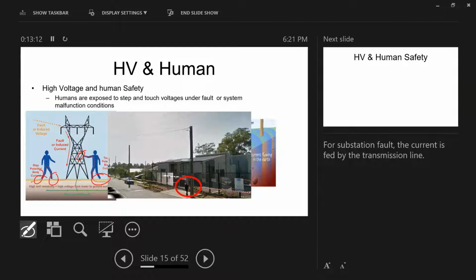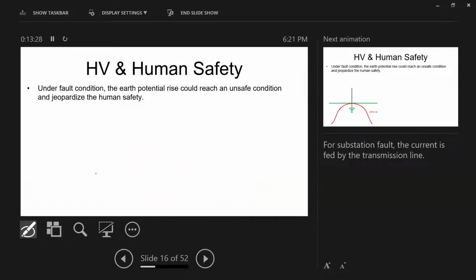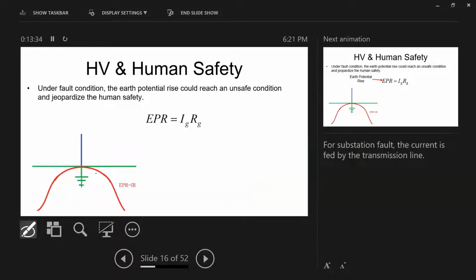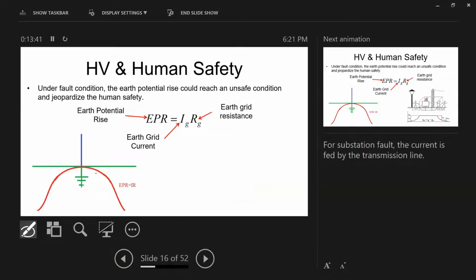One of the most important and critical, they call it in many countries a black art, is the earthing system, because you are designing and you don't know what's underground. We try our best to investigate our ground by injecting voltage and current, and I'll show you the most popular method that will be used for the system. So what will happen, guys, when a current goes into the ground? Ohm's law: the earth potential rise will be equal to the earth grid current multiplied by Rg, the grid resistance. This Rg is made of the soil of our earth at this location, plus or in relation to our electrode.